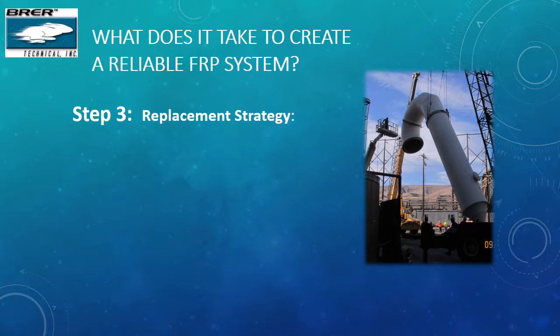You need to buy equipment that meets your goals for reliability and durability. Prices are being squeezed out there, and some suppliers respond by cutting corners. It's important to define the product you want by qualified design and specification before you go out to bid, with the understanding by all involved that there will be at least some knowledgeable shop inspection to ensure that the specification is observed. Even one random inspection and a telephone pre-job will help assure that the design and specification are used. Based on our experience, if you don't provide knowledgeable shop inspection, a proper design and specification may not be worth the cost.